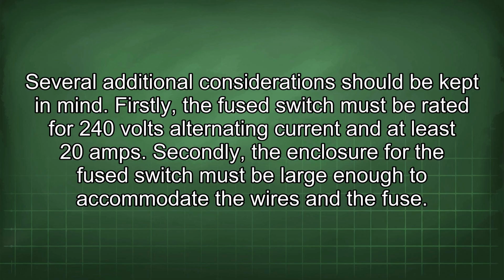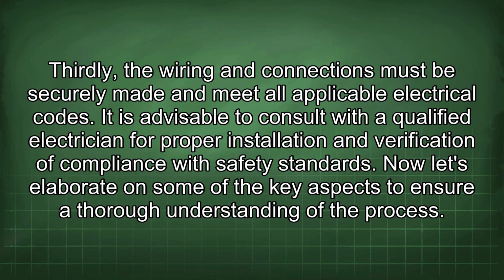Several additional considerations should be kept in mind. Firstly, the fuse switch must be rated for 240 volts alternating current and at least 20 amps. Secondly, the enclosure for the fuse switch must be large enough to accommodate the wires and the fuse. Thirdly, the wiring and connections must be securely made and meet all applicable electrical codes. It is advisable to consult with a qualified electrician for proper installation and verification of compliance with safety standards.